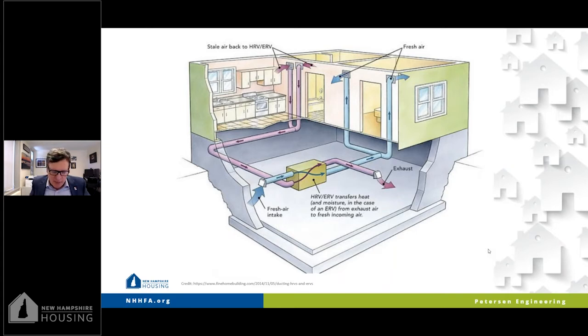Filtration has been a real focus over the last year. What can we do to filter air and help our cause in terms of transmission? With the ERV, there's really no filter incorporated into the unit itself. A better place for an improved filter is in the heating and cooling unit, which is oftentimes a fan coil unit, often a vertical fan coil unit. So filters with increased efficiency can often be retrofitted, and in new construction incorporated. We'll talk about filter efficiency in a minute.